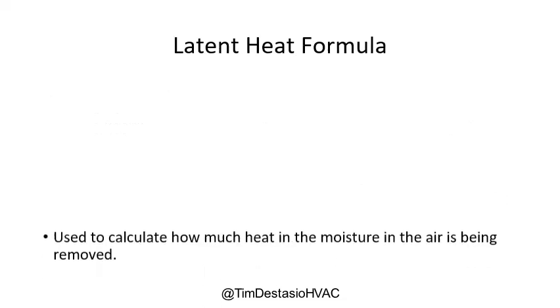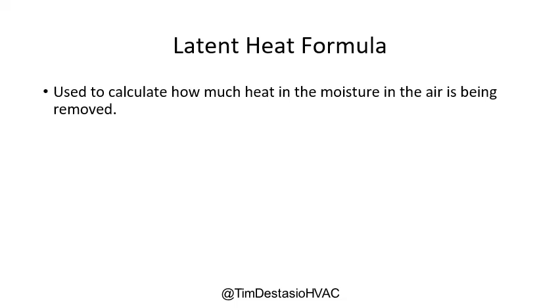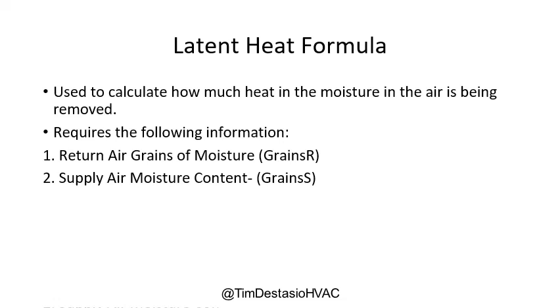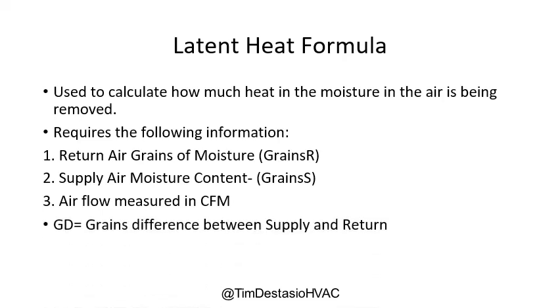With that knowledge, we can talk about the latent heat formula. It's used to calculate how much heat in the moisture of the air is being removed by an air conditioning system. To calculate latent heat, we need the grains of moisture on our return side and our supply side — how many grains before air passes through the evaporator coil, and how many grains after it leaves the evaporator coil. Just like the sensible heat formula, we'll also need to know how many CFMs of air we're moving. GD represents the grains difference between supply and return.